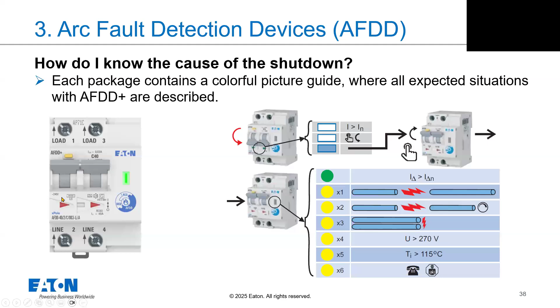If we look at the middle module, you can see symbols showing A-type, also temperature information down to -25. Regarding non-actuating time of 10 milliseconds, we are using G-type, meaning super high immunity against unwanted trippings. This is the RCD part, and the AFDD is according to the characteristics I presented earlier. There's no surprise regarding the MCB, it's standard, the RCD is A-type standard, and here we can see a bit bigger picture - only the AFDD characteristic is shown in the presentation or catalog.